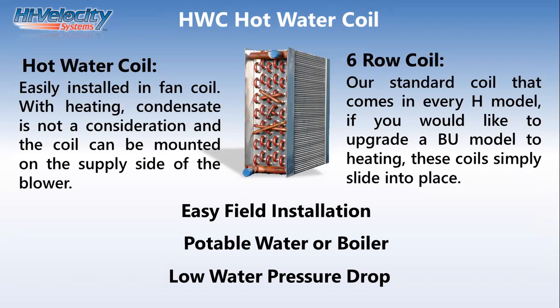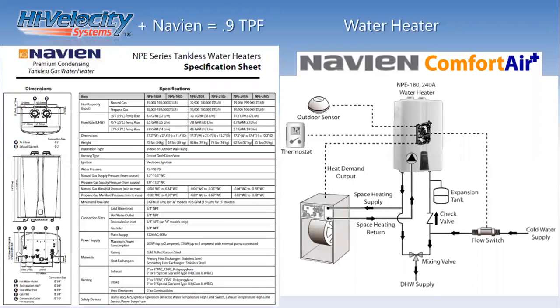In all of our products, we have a 6-row water coil, which gives us considerably better BTU output at lower entering water temperatures. That 6-row coil slides into the air handler, and it can be connected up to any water source. What we see most of in our market up here is a tankless type of technology like a Navien, Takagi, Rinnai type of water heater. And that technology has been proven to get better and better, and even working up in our cold Canadian -40 climates for heating. So a tank versus a tankless provides a ton of efficiencies on the tankless side by not having stored water heating and cooling all day with or without usage.